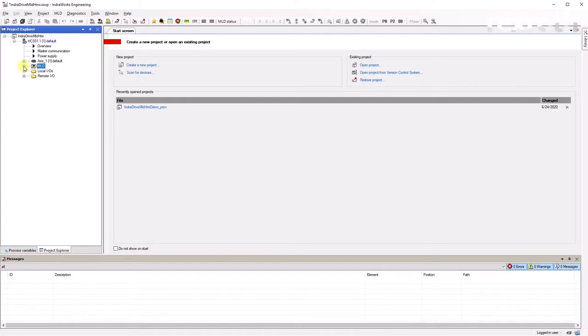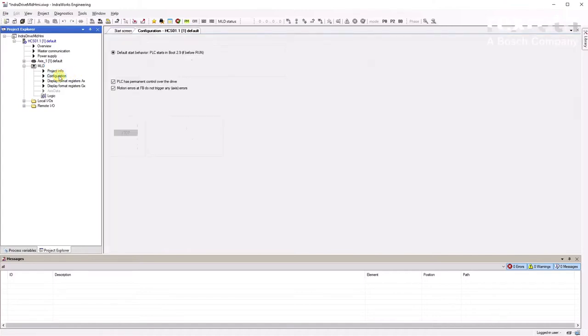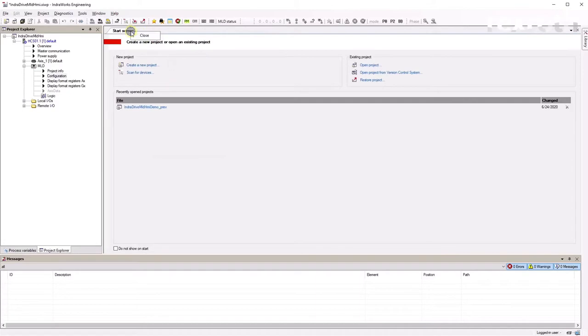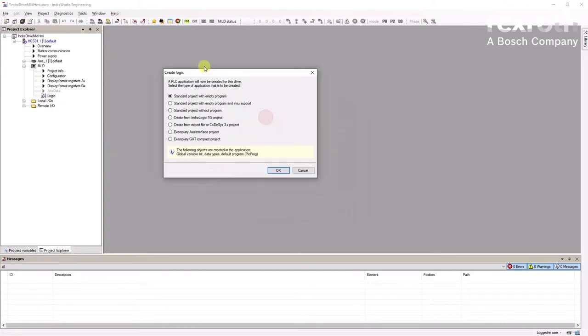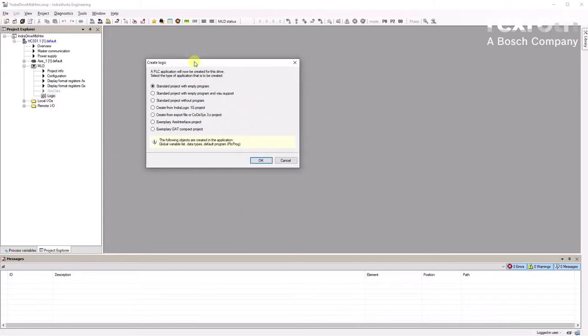In the drive you see that MLD is available. It's important to make sure that your MLD has permanent control over the drive — if this option is not checked on your system, please do it. Once done, close those two tabs and double-click on Logic. For this demo it's going to be very simple, so let's stay with the standard empty program and hit OK.